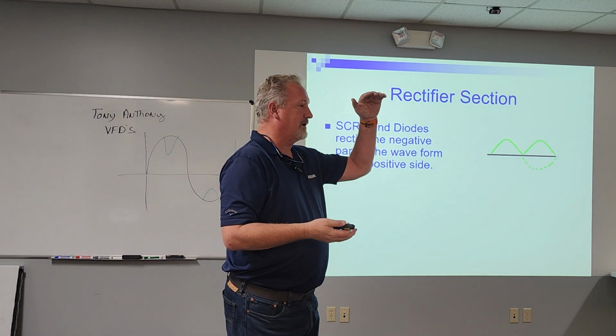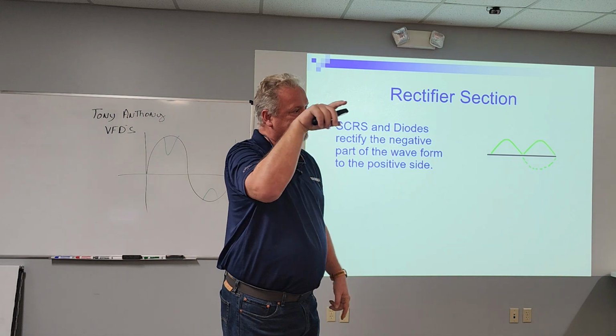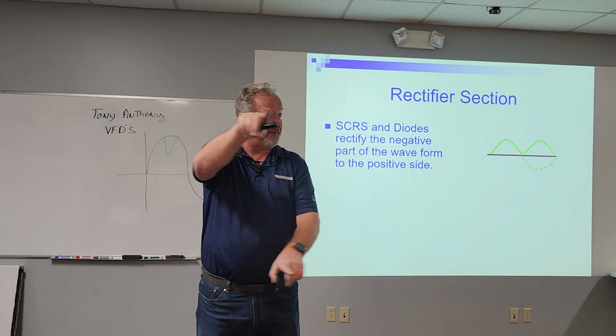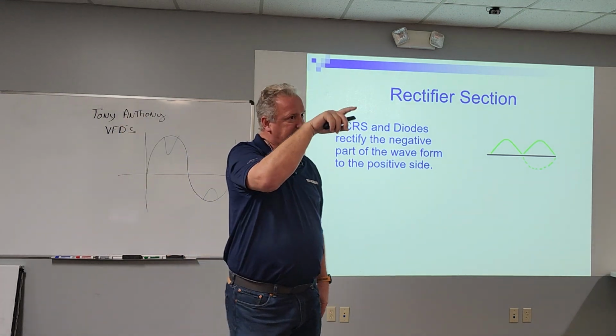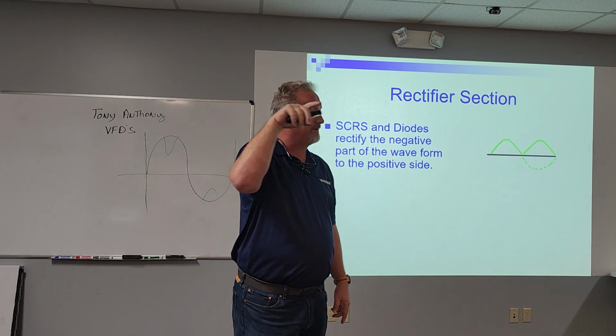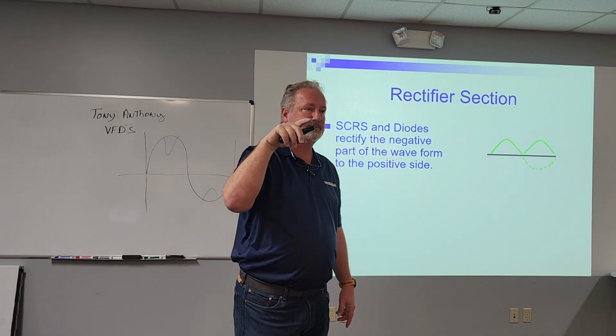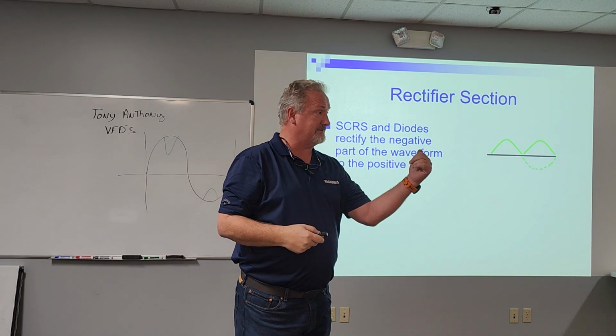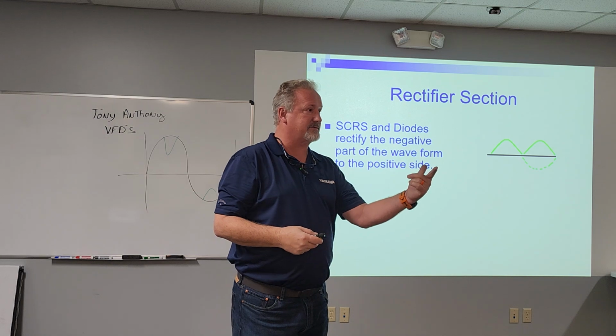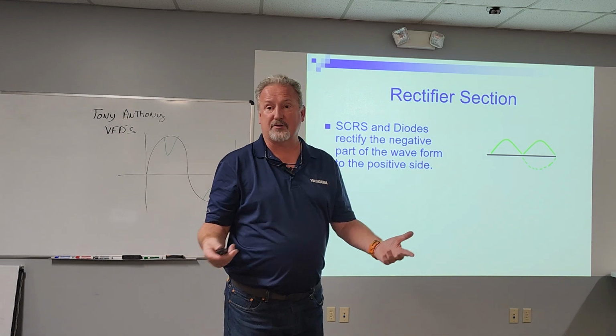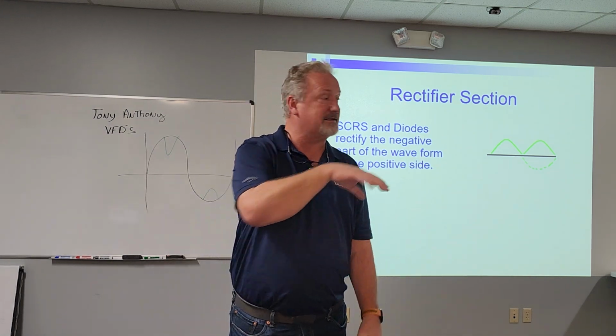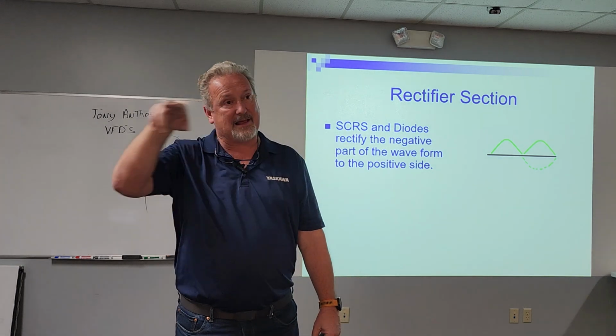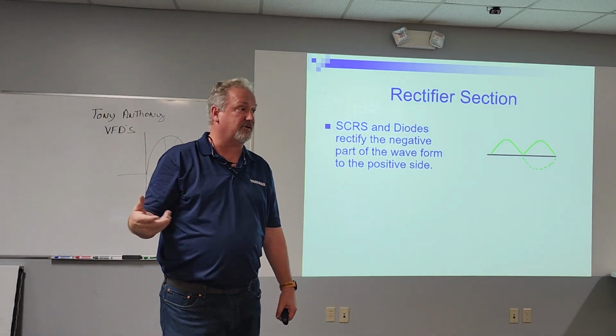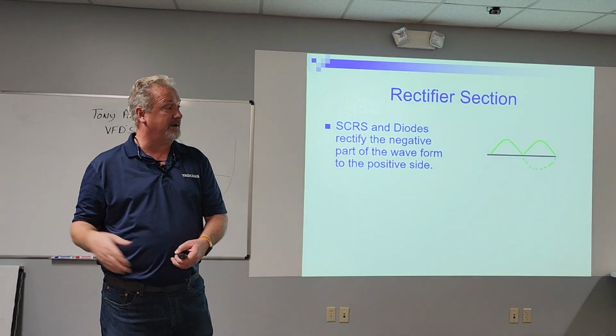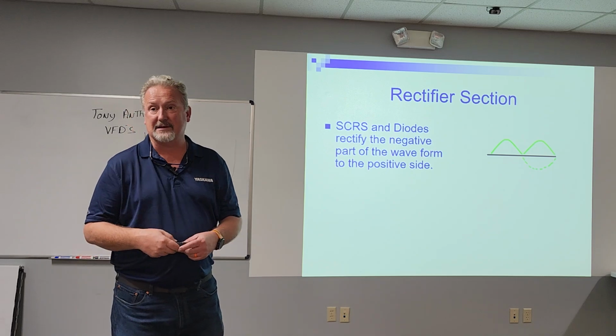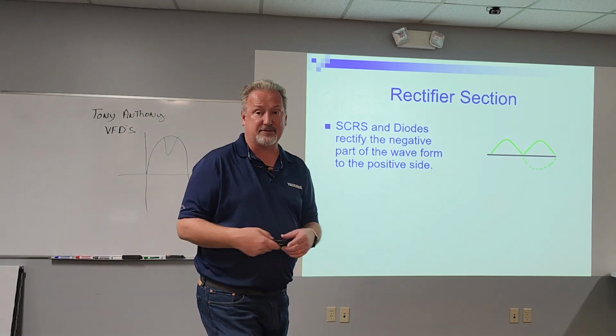There's a couple things we know. If you put a scope on it, instead of the DC, which should be a flat line, if you see a ripple on it, if that ripple gets more than 1 volt, you've got a problem. So you've either lost a phase or your capacitors are going bad. It's one of the ways we can troubleshoot a drive. Put a scope on that DC bus, and if it ain't a flat line, we know we probably are having troubles with our capacitors getting close to failure. It might be a time to look at replacing that drive or the capacitors at some point.